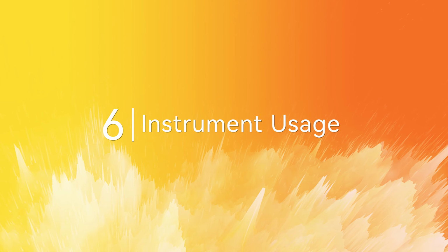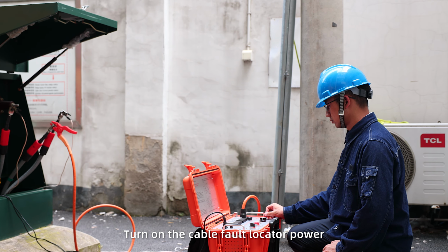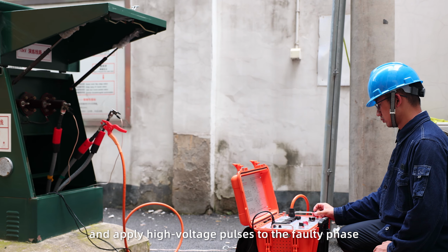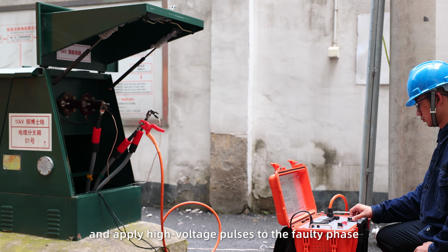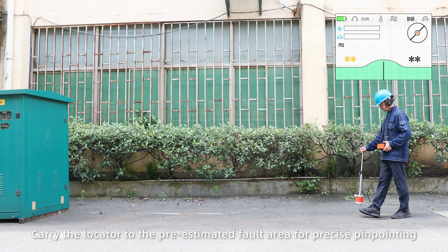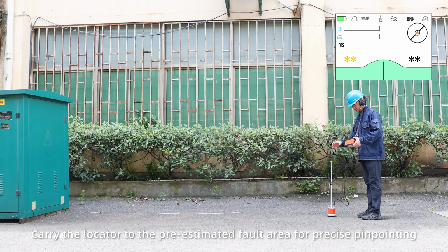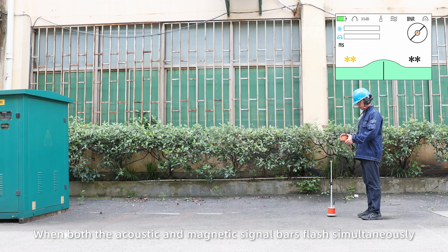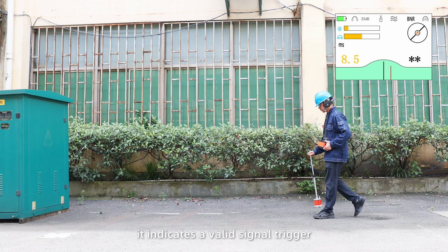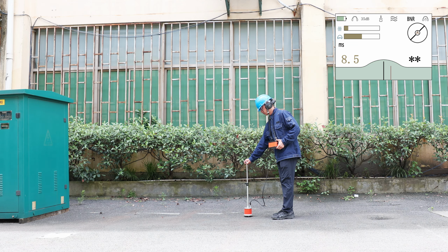6. Instrument usage. Turn on the cable fault locator power and apply high voltage pulses to the faulty phase. Carry the locator to the pre-estimated fault area for precise pinpointing. When both the acoustic and magnetic signal bars flash simultaneously, it indicates a valid signal trigger.